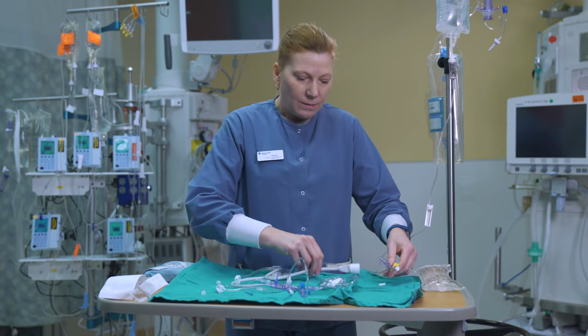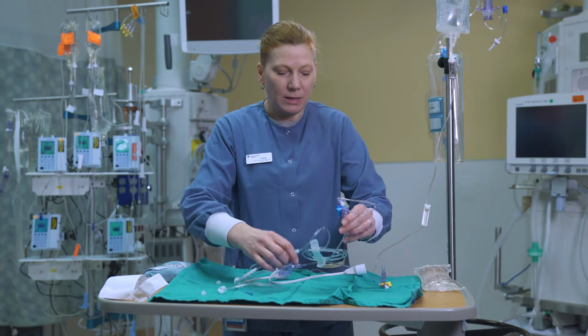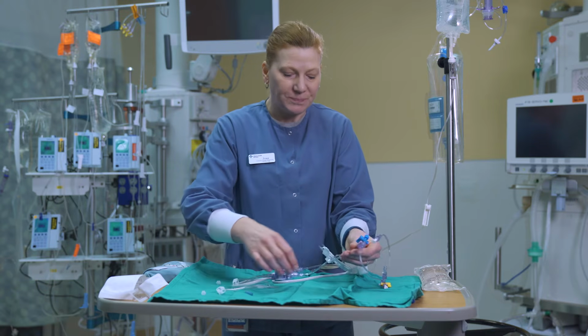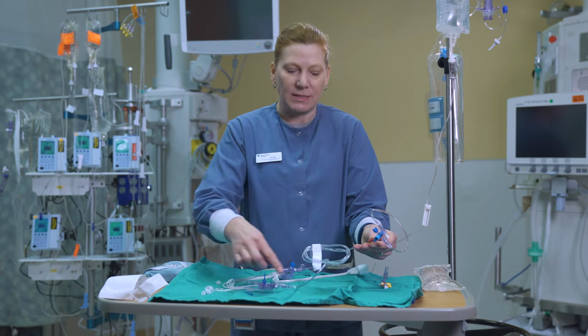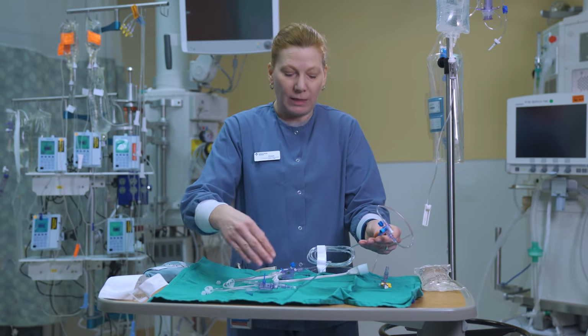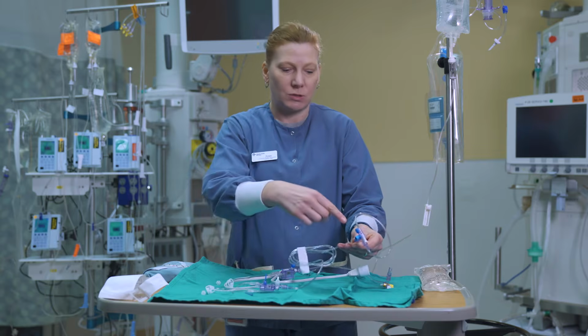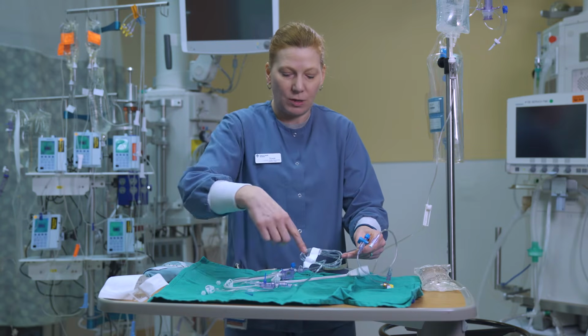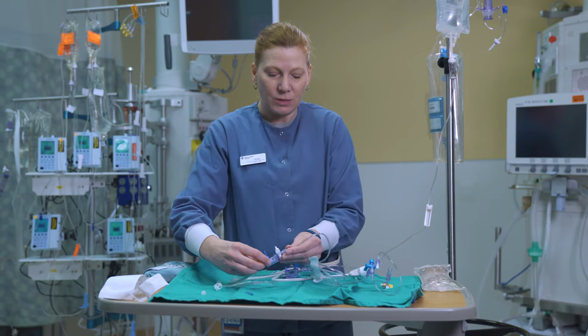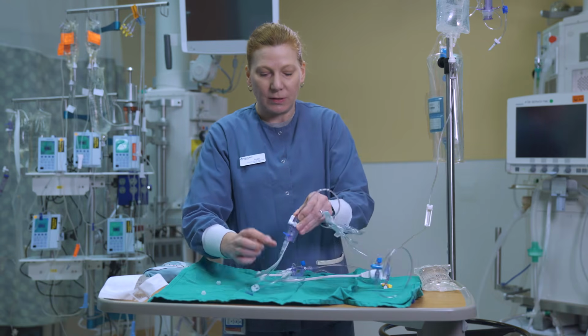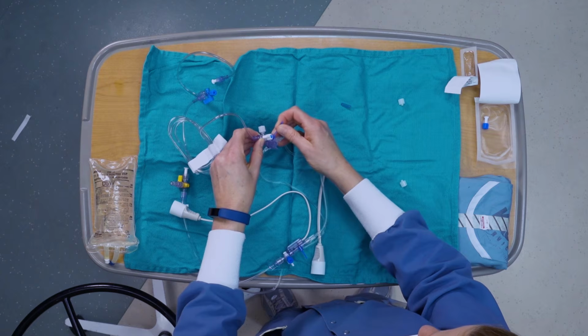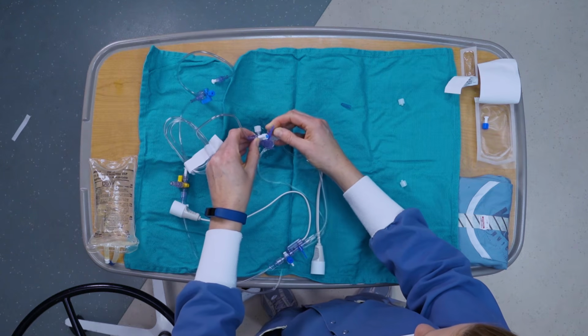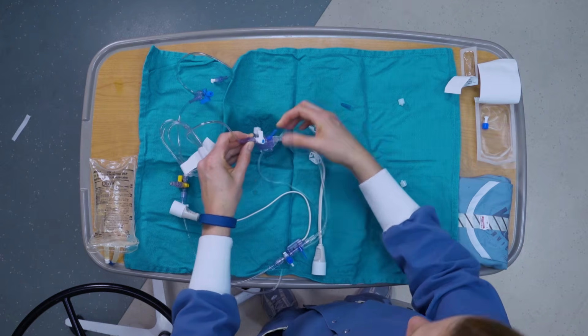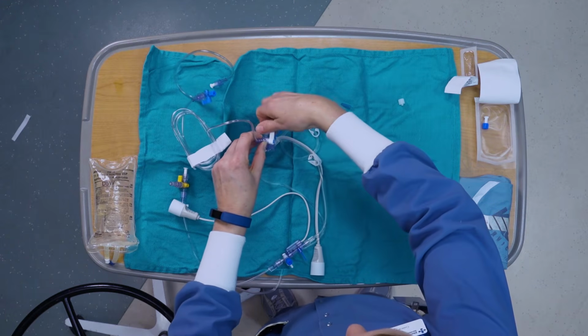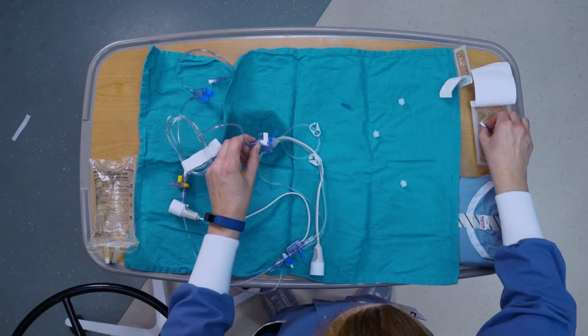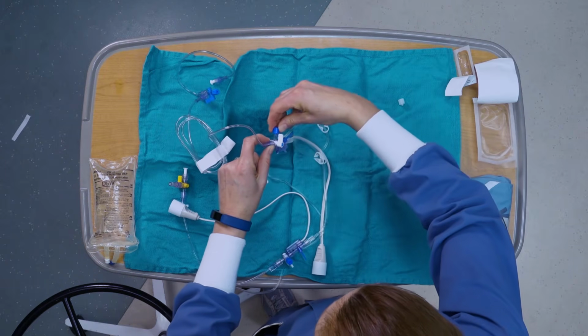Okay. The same process needs to be done for the CVP portion. In this case, I've left the tubing on, this extra piece of tubing. Normally, if you shortened one, you would shorten the other, but just so we can show you how it looks when there's the longer piece of tubing. So again, I'm going to go back to the transducer, and I'm just going to flush that through, make sure there's no bubbles in there. Okay. Once I've completed that and it looks good, I'm going to take off this white piece and put on the sterile, completely blocked off cap.